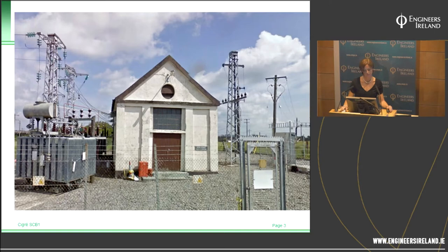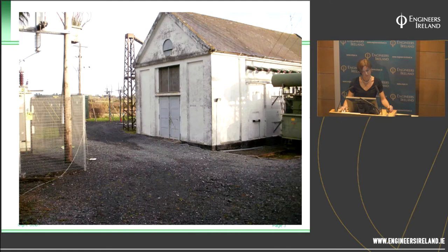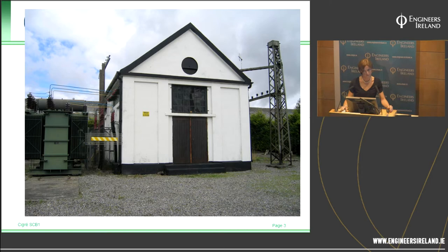That's a picture there of what we call a Siemens station. Siemens came to Ireland in the 1920s and built these as part of the national infrastructure for ESB. They're very German. They all look the exact same. And despite being almost 100 years old, some of them are still structurally in perfect condition. But they're very compact, and they were built on a very small piece of land. They have limited capacity, and once that's reached, no further lines can be taken out of the station. And often the switchgear inside was very old, and in some cases obsolete, which made maintenance and spare parts extremely challenging.